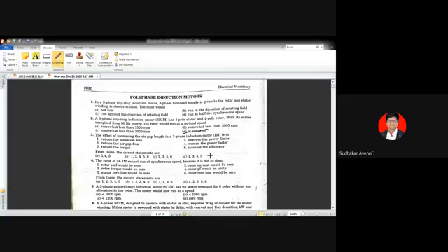Actually, what happens when we increase the air gap length between the stator and rotor? Generally, when we design induction machines, as much as possible we keep the air gap between the rotor and stator small, to improve the power factor and to increase the starting torque developed in an induction motor.